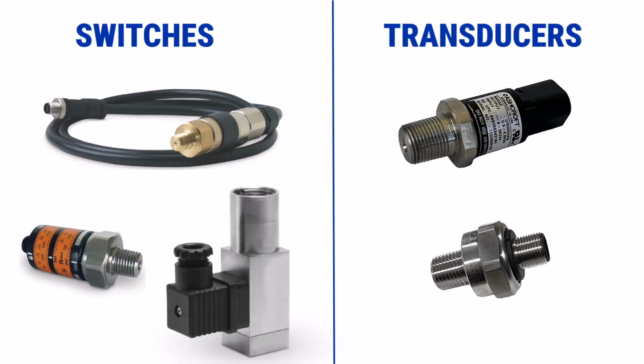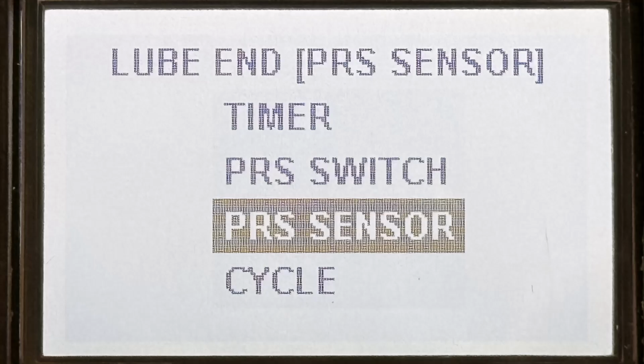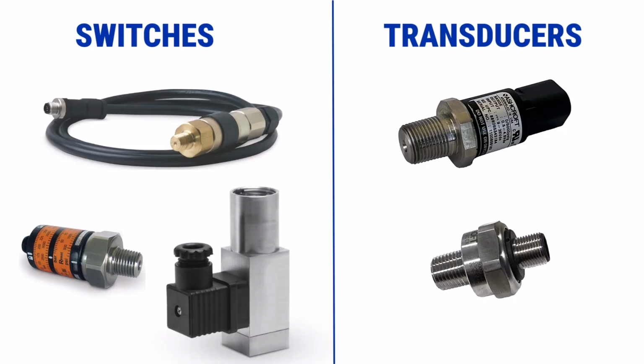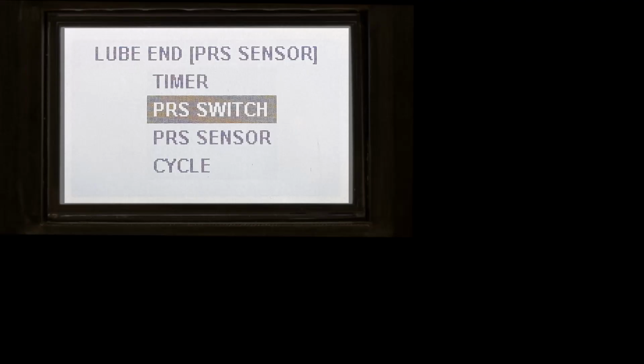For an injector system, you can choose to monitor pressure with either a digital switch or an analog transducer. The G3 setup menu uses the term sensor to refer to an analog transducer. A switch can be either a dry contact switch or a transistor, but either way, it's not the same as a transducer. So when you are programming the pump, be sure that you know which one you have, a switch or a transducer, and choose accordingly.